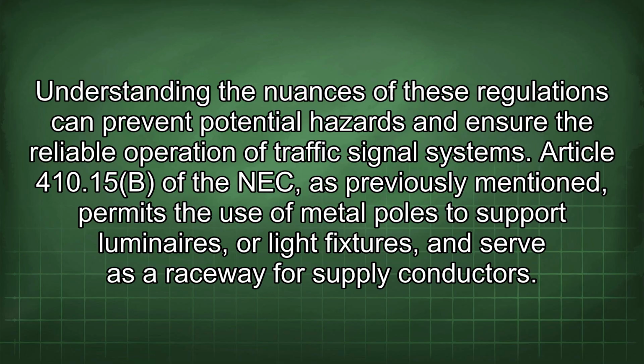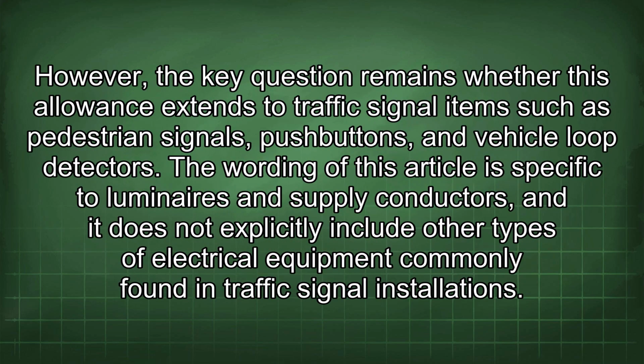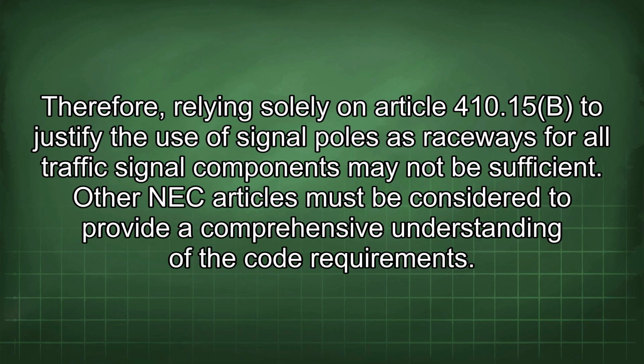Understanding the nuances of these regulations can prevent potential hazards and ensure the reliable operation of traffic signal systems. Article 410.15(B) of the NEC, as previously mentioned, permits the use of metal poles to support luminaires or light fixtures and serve as a raceway for supply conductors. However, the key question remains whether this allowance extends to traffic signal items such as pedestrian signals, push buttons, and vehicle loop detectors. The wording of this article is specific to luminaires and supply conductors, and it does not explicitly include other types of electrical equipment commonly found in traffic signal installations. Therefore, relying solely on Article 410.15(B) to justify the use of signal poles as raceways for all traffic signal components may not be sufficient. Other NEC articles must be considered to provide a comprehensive understanding of the code requirements.